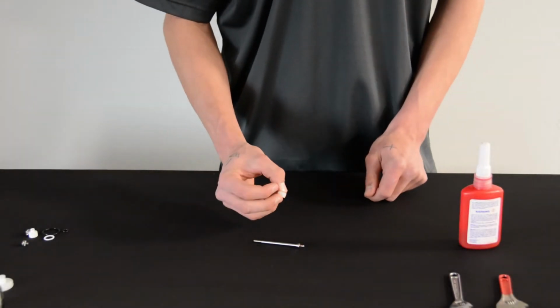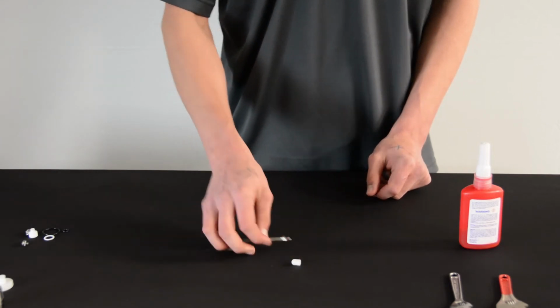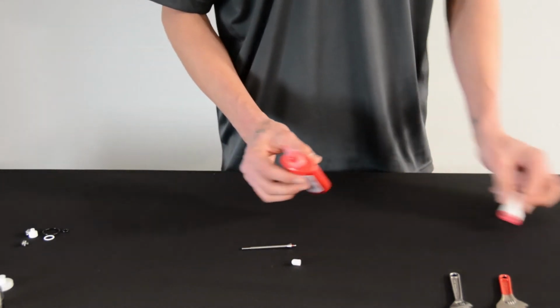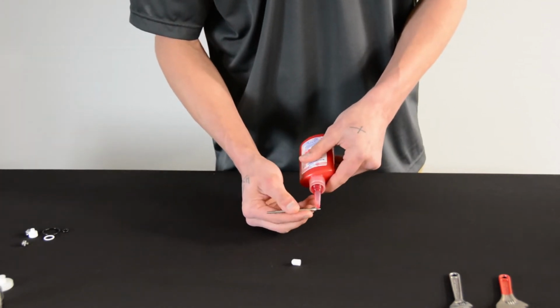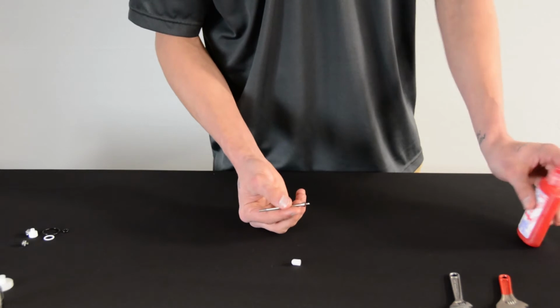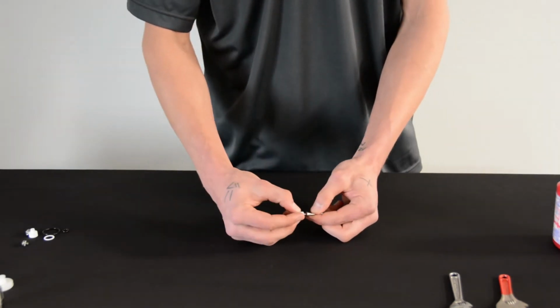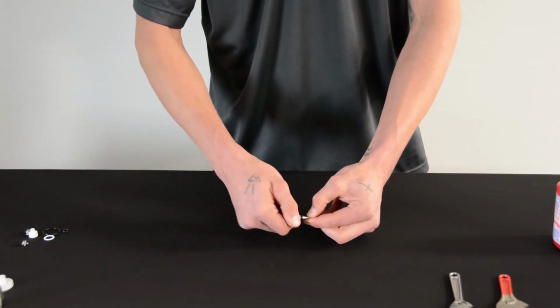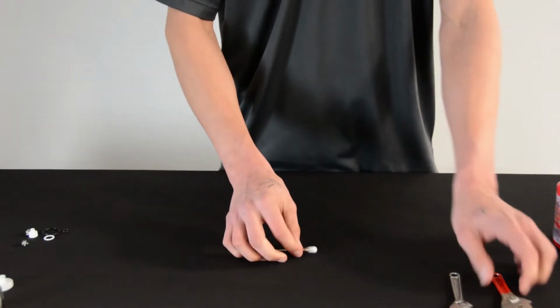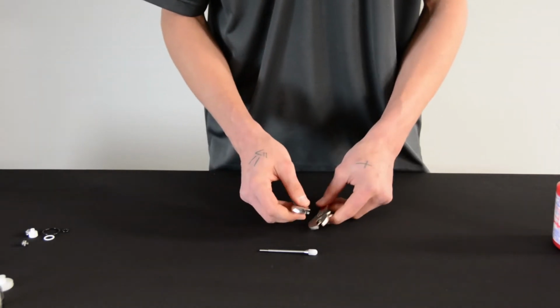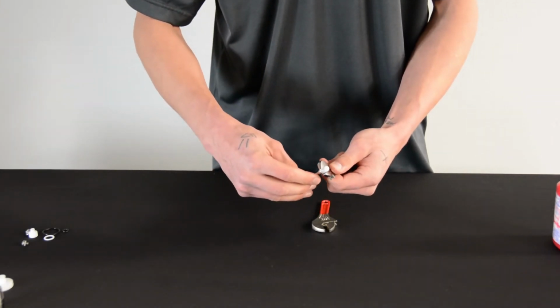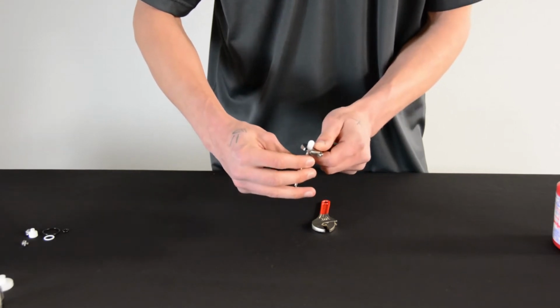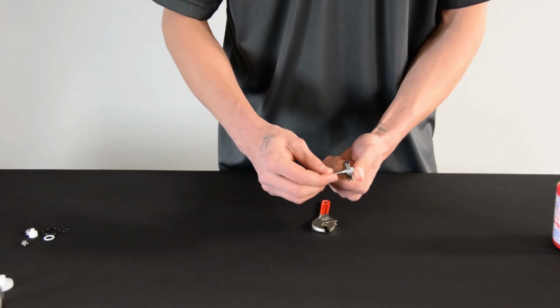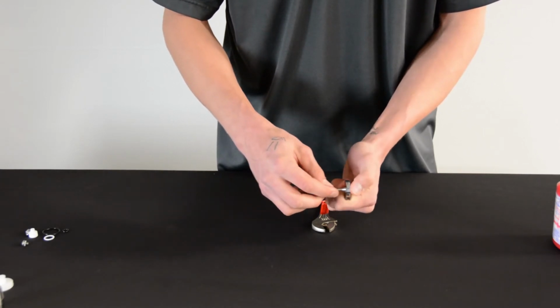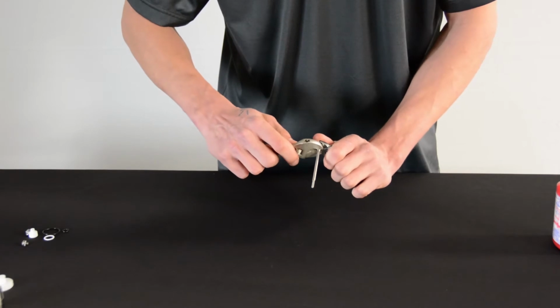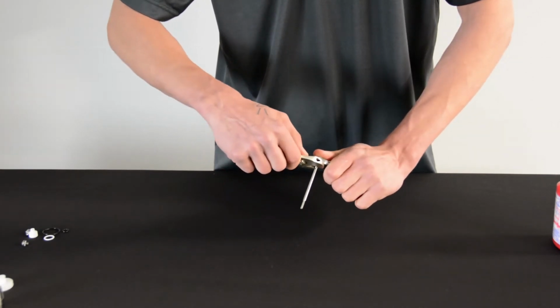First, we're going to take our new plunger end from our Poppet valve repair kit and our piston shaft. Take a little bit of red Loctite and apply it to the threads on the piston shaft. Then take your plunger end and screw on to the end of the piston shaft. Once it is fully finger tightened, take your two 9/32 wrenches or small adjustable wrenches and tighten the plunger end onto the piston shaft. It is important that you don't over tighten over 90 degrees.